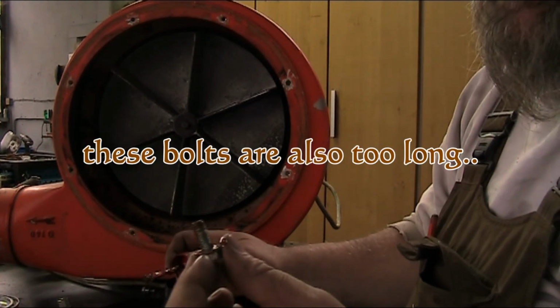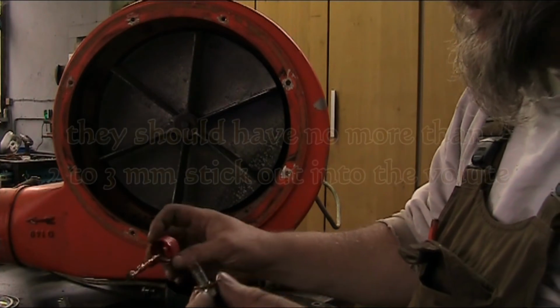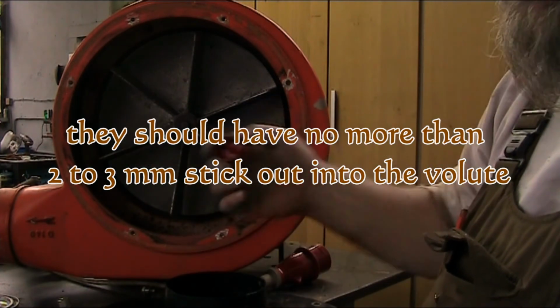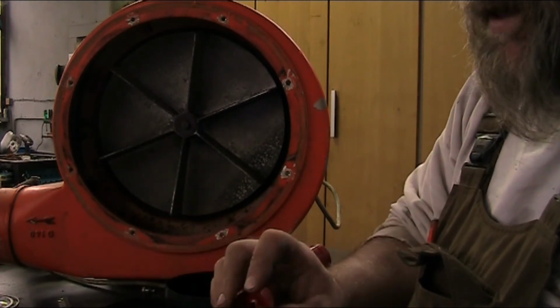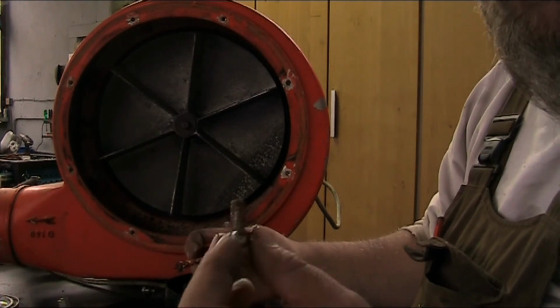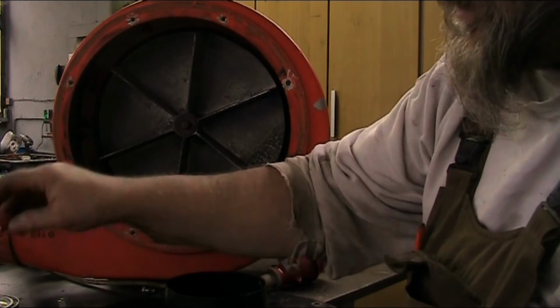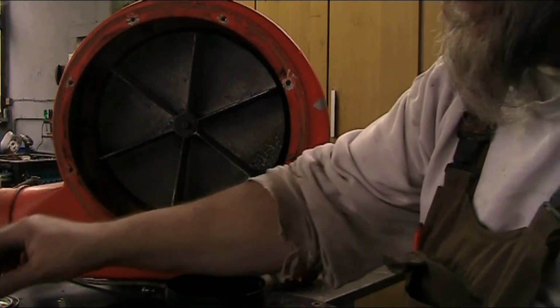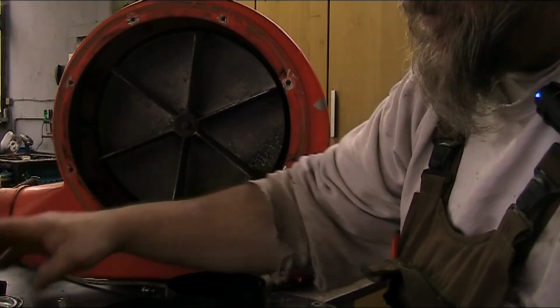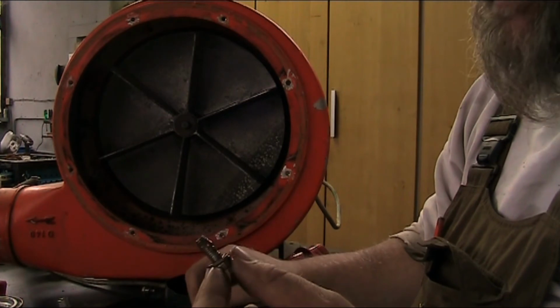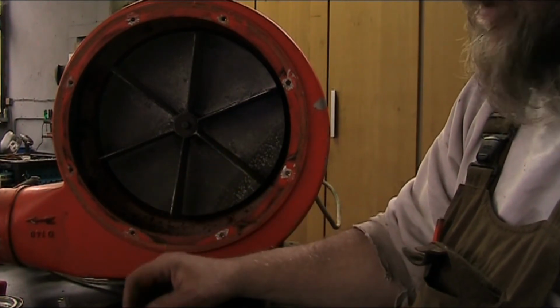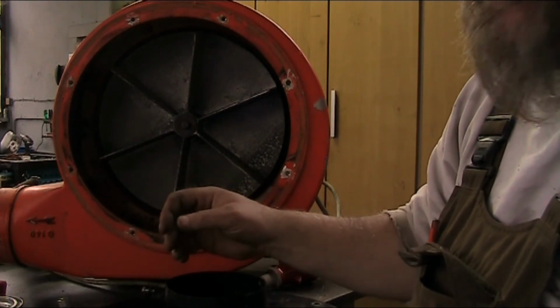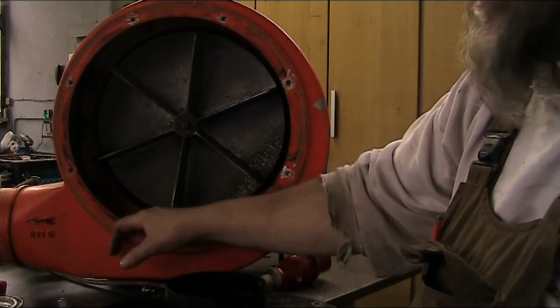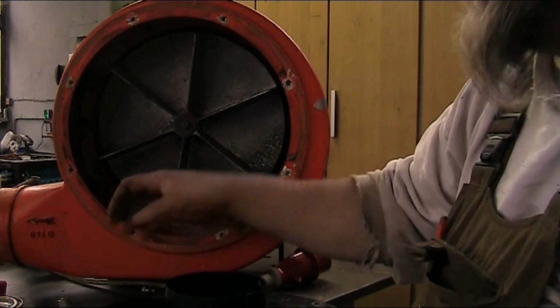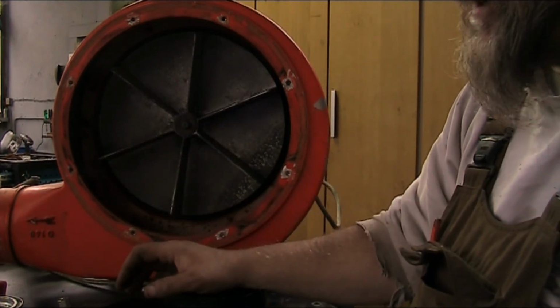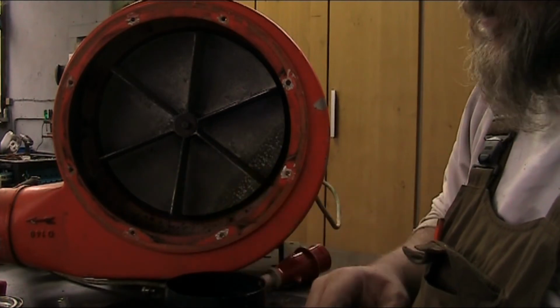And they are galvanized. So the one problem I was having, and this is the reason this screw didn't come out very well, is there was a galvanic reaction between the zinc of the bolt and the aluminum of the housing. So one of the things you've got to do is put a little bit of copper paste onto these bolts before you run them in. Otherwise you're going to run into that same problem again, where the galvanic reaction will cause the bolt to seize. That's always a problem. And because these things do load up with static discharge or static electricity, that again accelerates the galvanic reaction. So you've got to make sure you mitigate for some of these things going in.